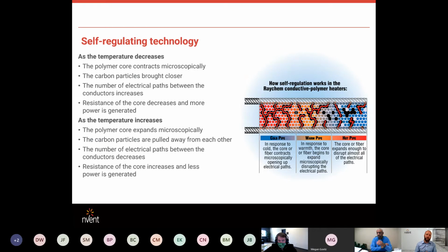However, when you get into uncontrolled systems, and you're trying to rely on self-regulating cable to maintain the temperature, we can get into over-temperature issues. What I have seen numerous times through the years is exactly that on the safety shower line. They use even our lowest output cable, our 3 BTV cable, at 3 watts per foot. They will put that on the pipe, put it on a breaker, no thermostat, and just let it cook. That way they know, okay, we have a breaker and a cable, minimal points of failure, it should be reliable and always on.